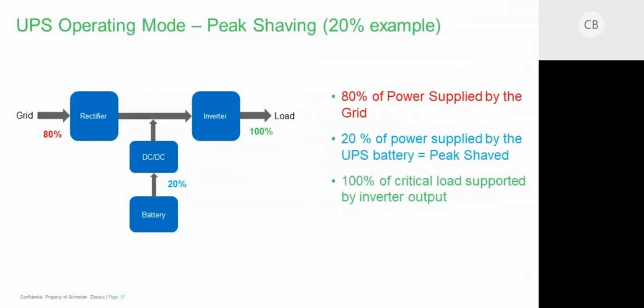So this is kind of illustrative of how it works. You don't have to switch 100% from the grid to the battery plant on the UPS. The software will control it, and you can preset how much peak shaving you want to do. So you may be supporting the load with 80% from the utility grid and 20% from your battery plant. And remember, this isn't full time. You're not operating in this mode 24 hours a day. You're operating in this mode at the right times of day where you can shave that peak and reduce that kW demand charge on your utility bill. Next slide.